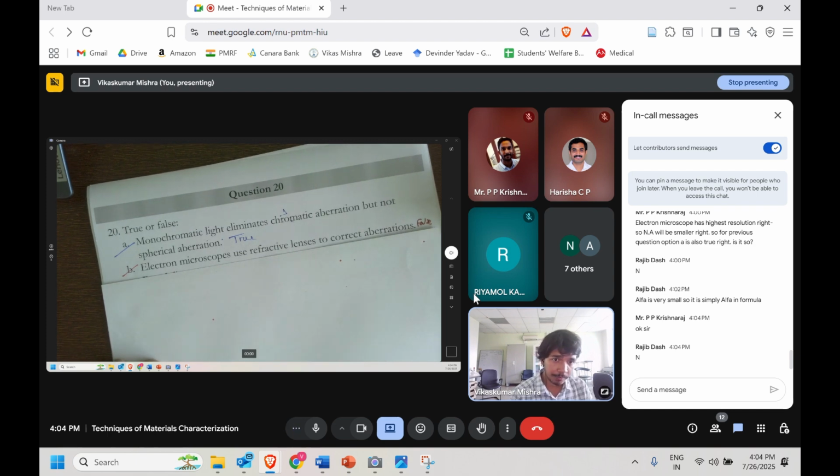It uses the condenser lens and all those things. Let's say some aberration is there in the astigmatism, let's talk about that. We know that the power of one axis is focusing somewhere else, and the vertical is focusing somewhere else, horizontal is focusing somewhere else. So you can change the strength of the field and converge the electrons in such a way that now they are going to coincide. The vertical and the horizontal should coincide with each other, at the point where they are focusing.